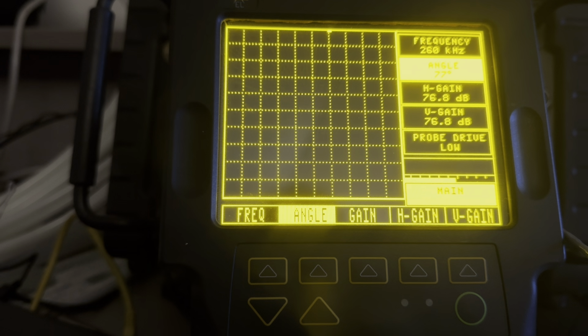Anyway, these series of testers, the Nortec 1000s, the 1000S, the 1000. Then they did the 2000, which was still a single frequency. Then they did a 2000D, which was a dual frequency flaw detector. Then they did the D+, which added a color display. And then there was a Nortec 2000D Plus EMI, and the EMI didn't really add a lot other than it was designed to meet certain requirements for not emitting electromagnetic interference, and that was specifically for the military, I guess. So if you're out there shopping for one of these used ones and you see a 2000D Plus and a 2000D Plus EMI, you can forget about the EMI and get the other one, or buy either one, but you're not getting anything extra if you go for the EMI.